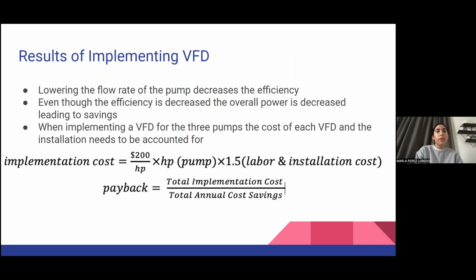Okay, so for implementing a VFD, it would lower the flow rate of the pump, and then that leads to a decrease in efficiency. But even though the efficiency is decreased, the overall power is decreased. And so when we implement a VFD, we need to take account of the 3 pumps and the cost of each VFD, and then the installation costs. So then I came up with the equation. For every horsepower, it's $200, and then you would just multiply it by the horsepower of each pump, depending if they have different horsepower, and then the labor cost and installation is a factor of 1.5, and then the payback would be the total implementation cost divided by the total annual cost savings.